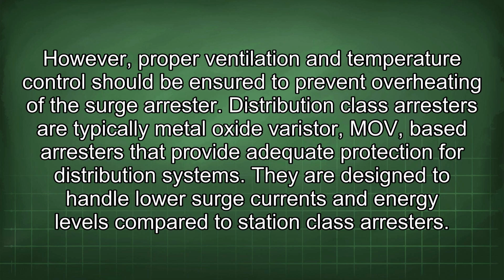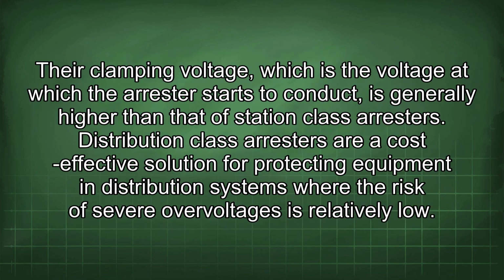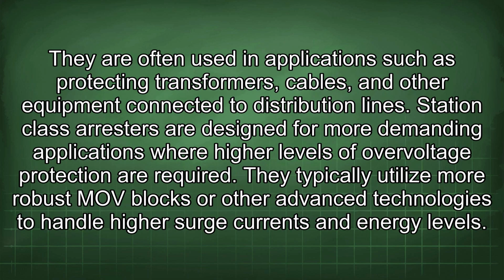Distribution class arresters are typically metal oxide varistor, MOV, based arresters that provide adequate protection for distribution systems. They are designed to handle lower surge currents and energy levels compared to station class arresters. Their clamping voltage, which is the voltage at which the arrestor starts to conduct, is generally higher than that of station class arresters. Distribution class arresters are a cost-effective solution for protecting equipment in distribution systems where the risk of severe overvoltages is relatively low. They are often used in applications such as protecting transformers, cables, and other equipment connected to distribution lines.